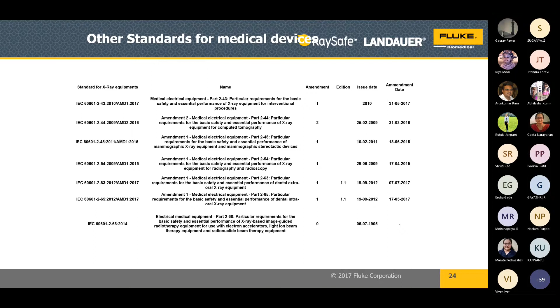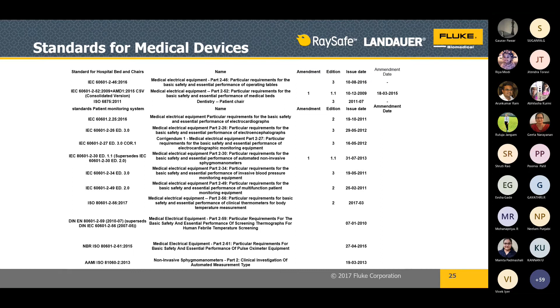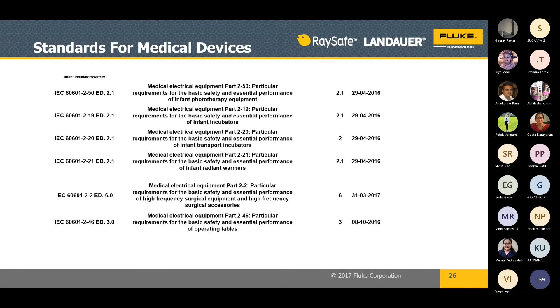Now we have other standards for medical devices. For all equipment, the standards are different. Like you see on this slide: medical electrical equipment, particular requirements for basic safety and essential performance, X-ray equipment. For all radiation management equipment, we have these kinds of standards. Then hospital beds and chairs, then incubators and warmers. All those standards are different, and for that you have independent equipment for each standard to fulfill.